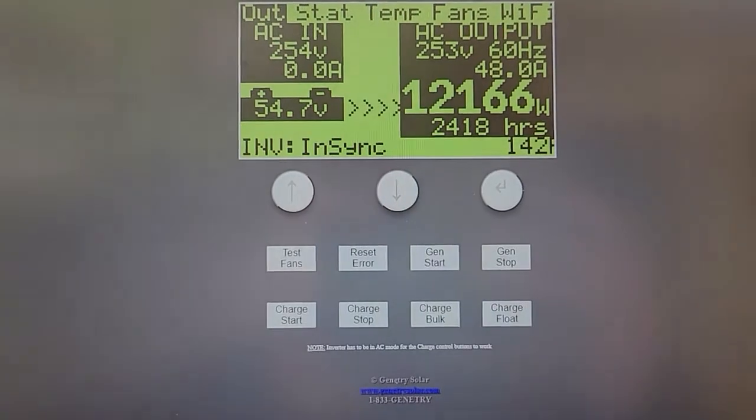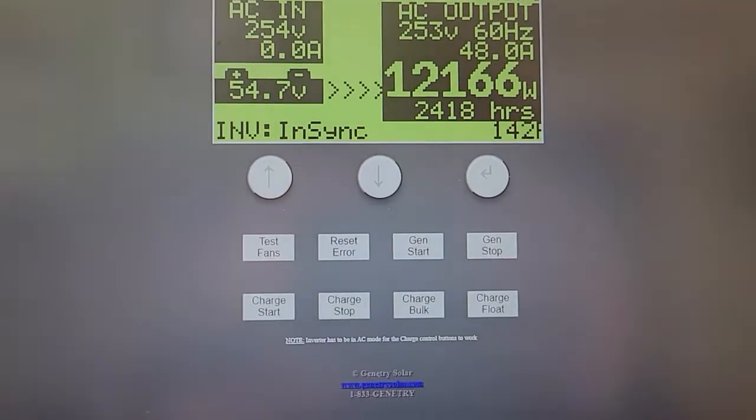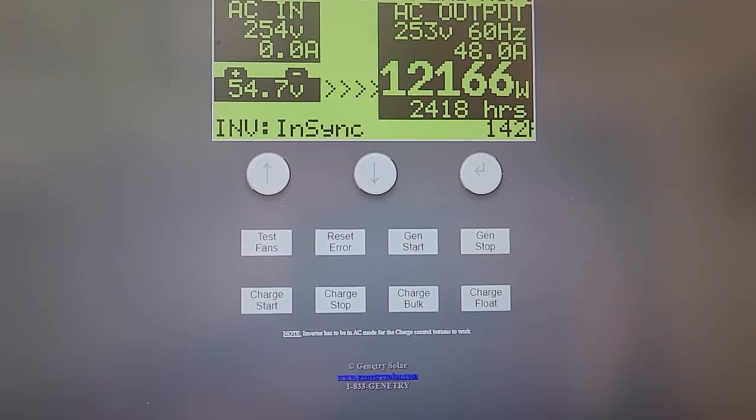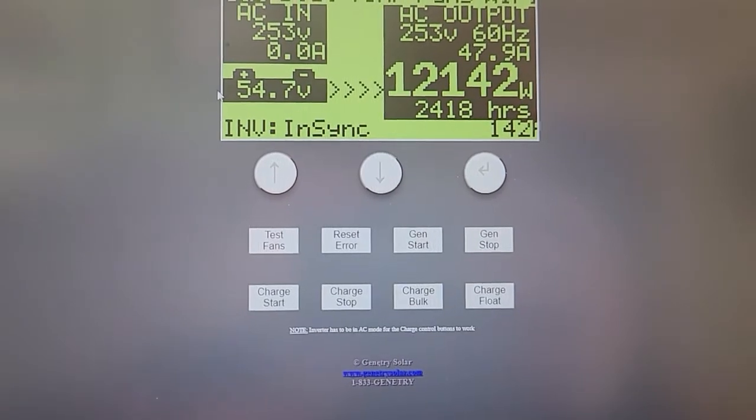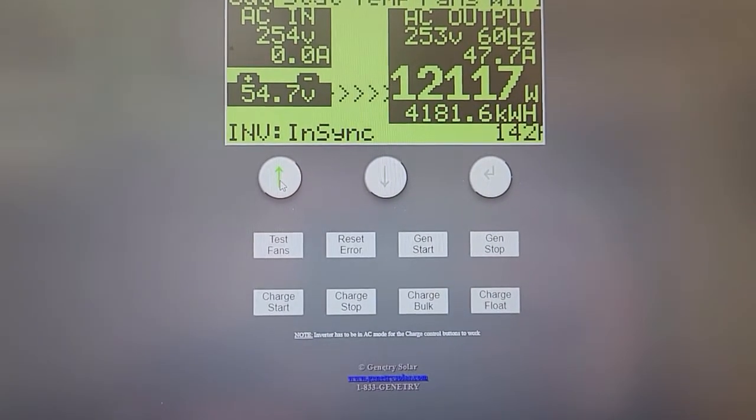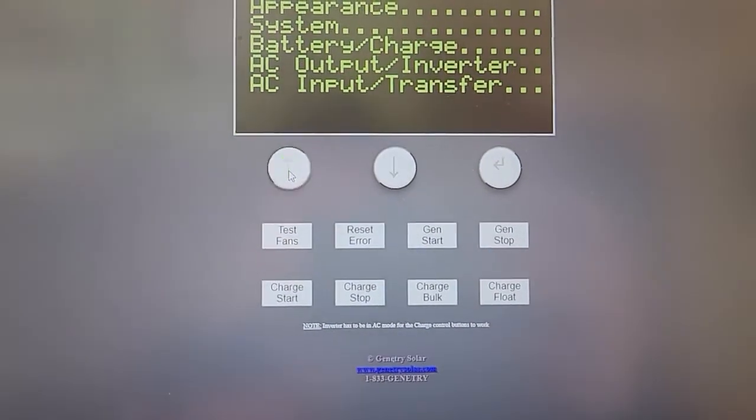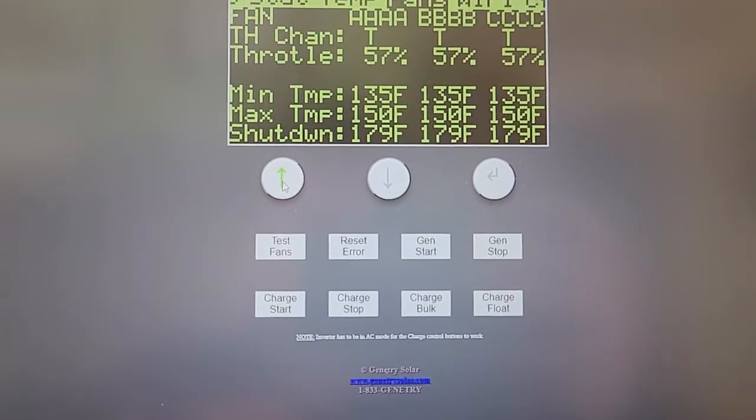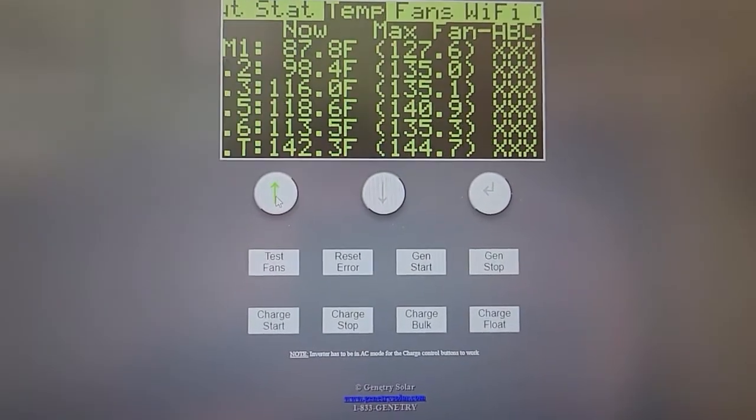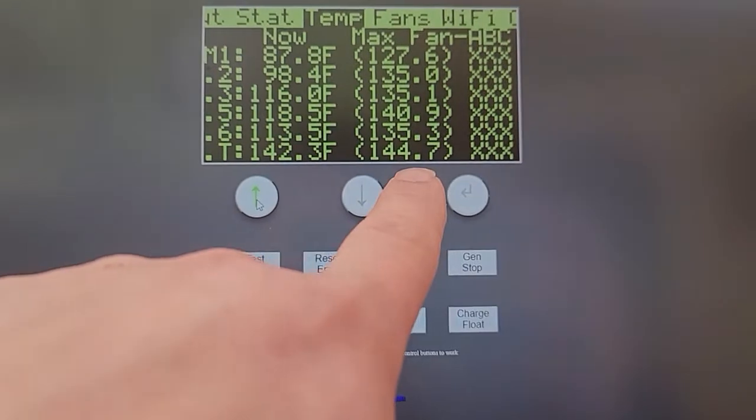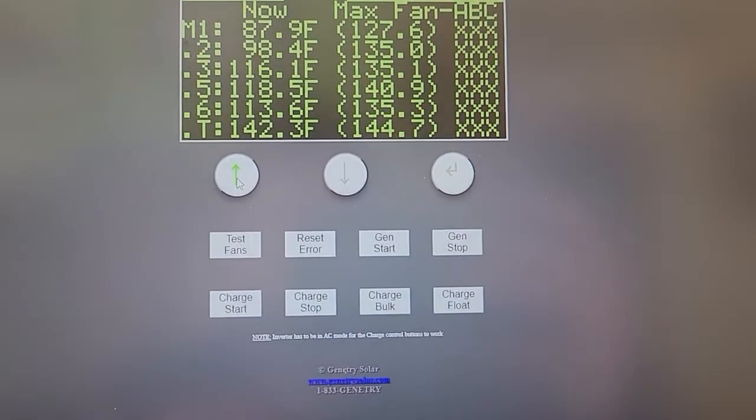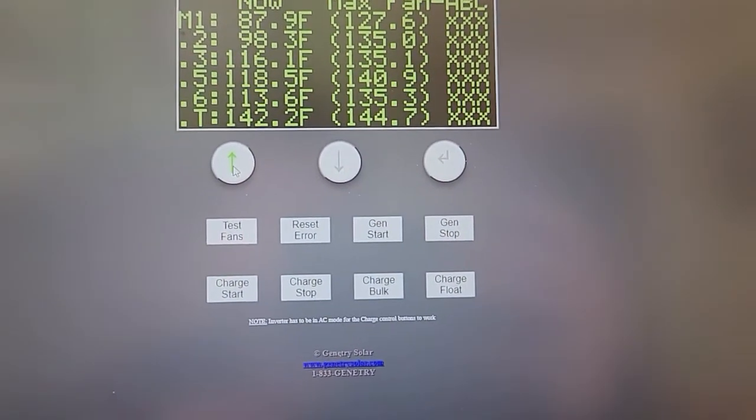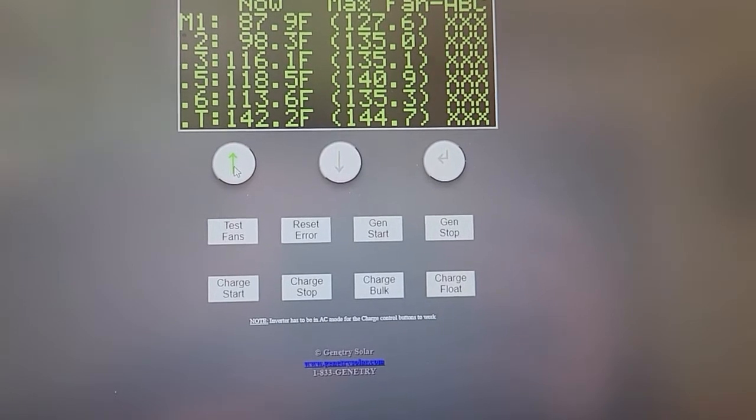I know that's not a lot of time. But consider that with this load here, if this was a runaway load where it's going to overheat, we would see it right away. And what we are actually seeing here, let's look, fan speed is at 57 percent. Temperatures have not exceeded 144.7 degrees.